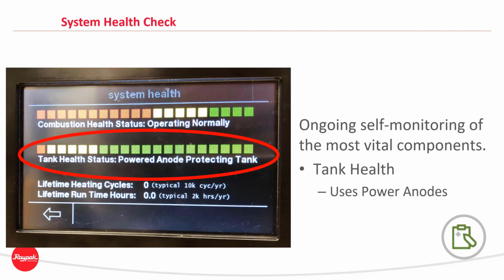Here we see the system's health screen on the display. In the tank health bar, one box will be flashing, indicating the status of the tank. As the glass lining gradually wears out over time, and it will, as it does in all glass-lined tanks, the powered anode will increase their power output and the flashing box will gradually move to the left. When they are approaching maximum power output, you will get an alert. You will get another alert when the anodes reach maximum power output, indicating the tank is near end of life.